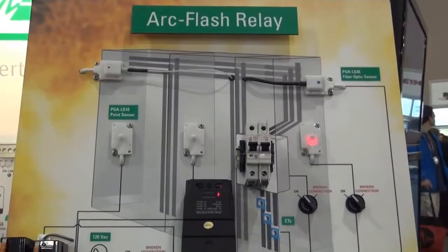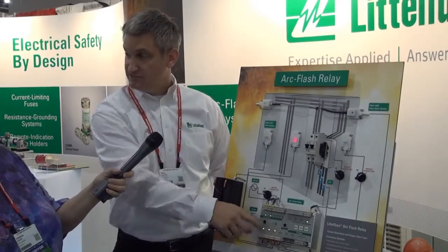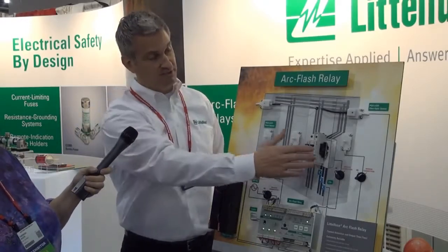Now, there are a couple of features here I want to highlight, because an arc flash relay has the ability to lower your PPE. So if it does that, it must be highly reliable, have several different redundant features to it, and be easy to use. As you can see here, the sensors are blinking twice. That means they're active. If for some reason one sensor were to fail, and I'll simulate that by switching that switcher, you can see there's no longer blinking. And after a period of time delay here, the relay sees that the sensor is not wired properly, something is wrong. So it alerts the user to come out and repair the sensor, or it also prevents a user from working in that cabinet because he's not protected.